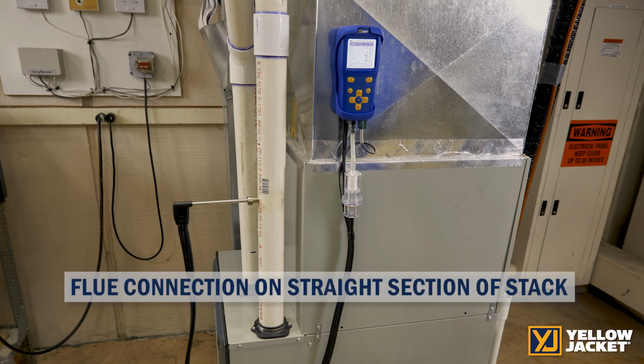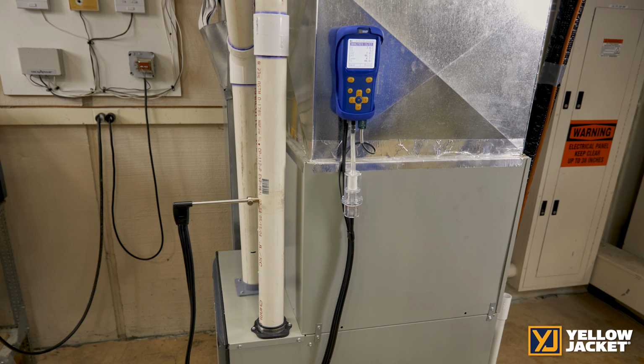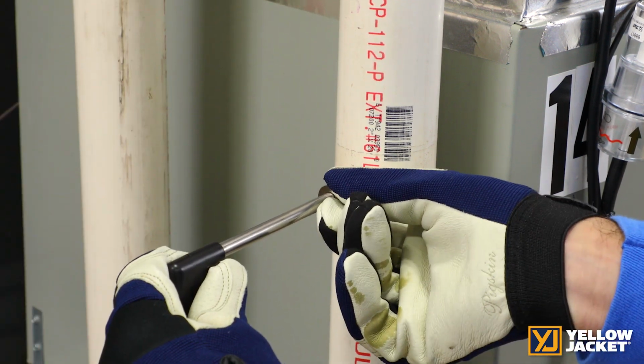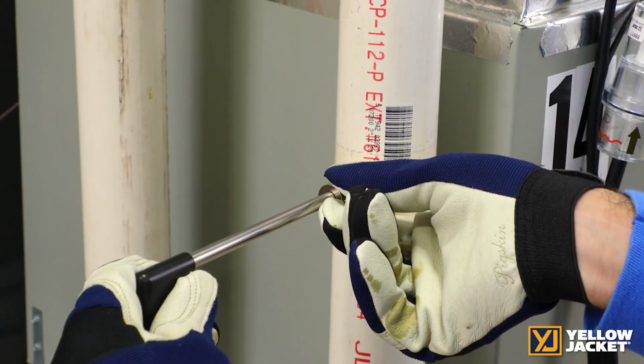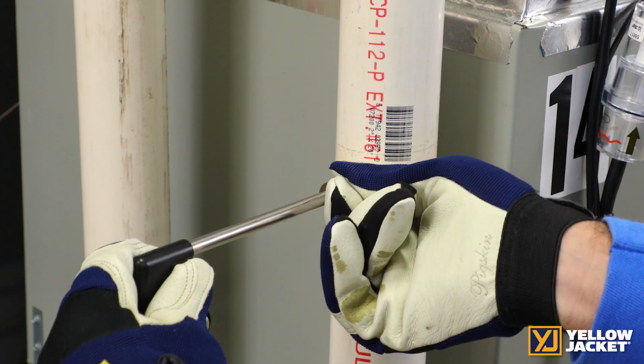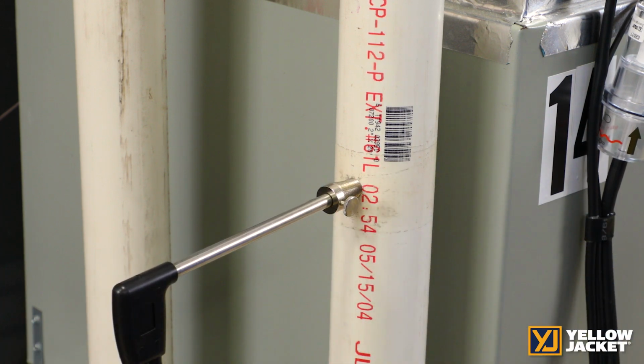Ensure that your flue connection is on a straight section of stack, as you do not want it to be near bends where the readings may not be gathering the entire flue sample. Push the probe all the way back to the back of the flue and then pull out halfway to ensure the probe is centered in the flue.